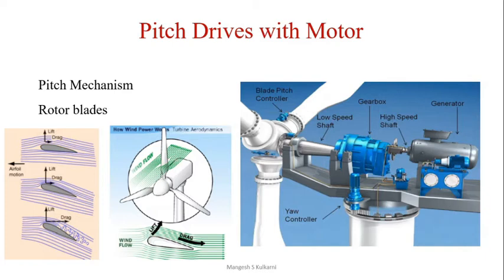The motors of the pitching system have an intelligent system with frequency control drives controlled by their own controllers. These intelligent frequency drives communicate with the control system in real time. The control system updates the motor after gauging the available wind regime, and the motors constantly update the control system on the instant blade angle. The precision electromechanical micropitch mechanism achieves 0.1 degree pitching resolution, resulting in extreme fine-tuning of the aerodynamic profile.